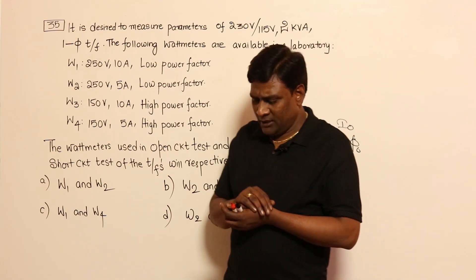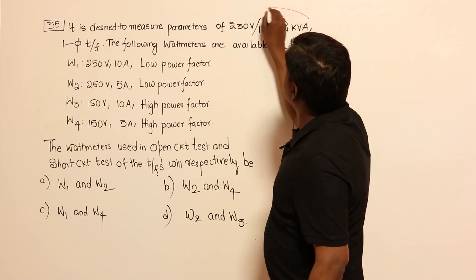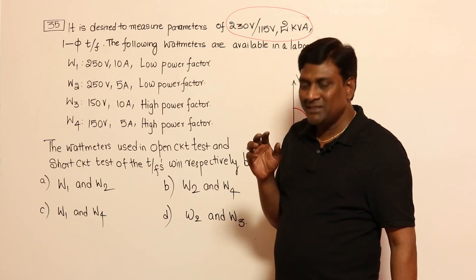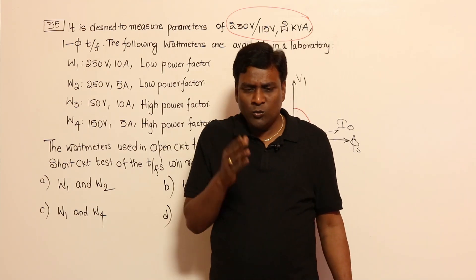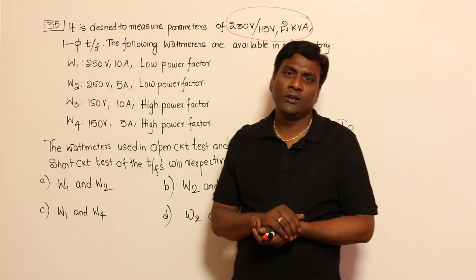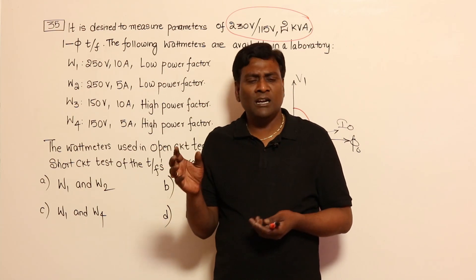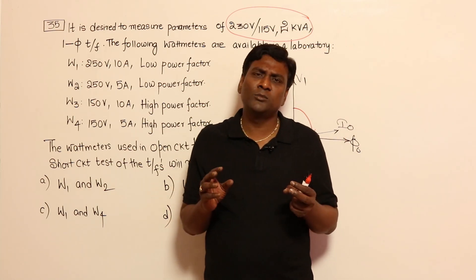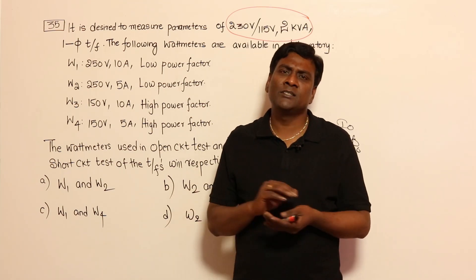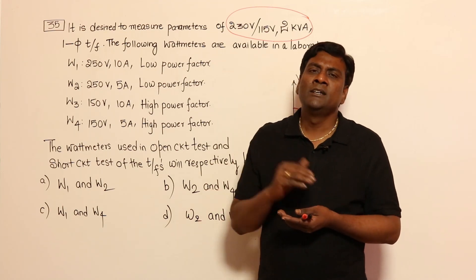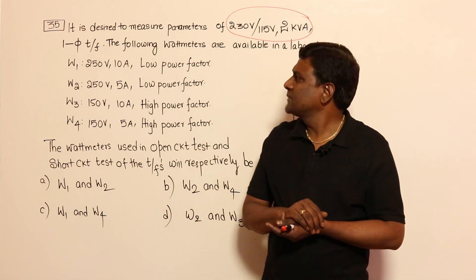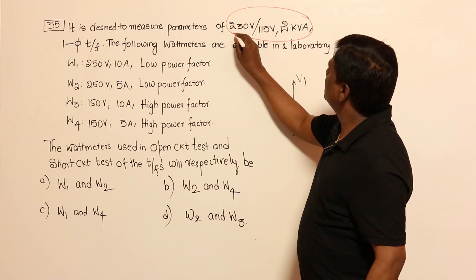So for solving this problem: LPF for OC test, HPF for SC test — please consider this. Now, a very popular misconception is that OC test should be conducted on the LV side and SC test on the HV side — this is completely wrong. There is no such specification. Very substandard books have written that. This discussion I'll keep for detailed machine analysis, as that question won't come in GATE 2020.